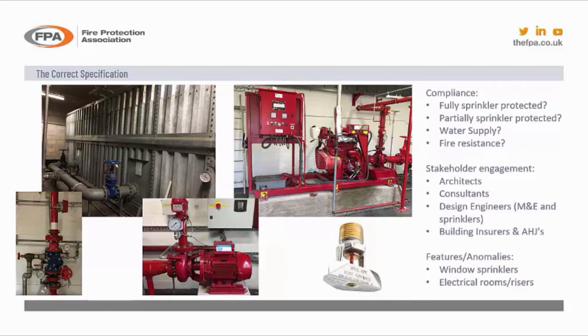These are little incidental issues that need to be considered for compliance with the standard that is selected at the beginning. So this must be confirmed in the specification. Then we move on to stakeholder engagement. Has everybody with an interest in the building and fire protection been considered? The list shown is not exhaustive, but those shown should always be involved in the specification of the sprinkler system.